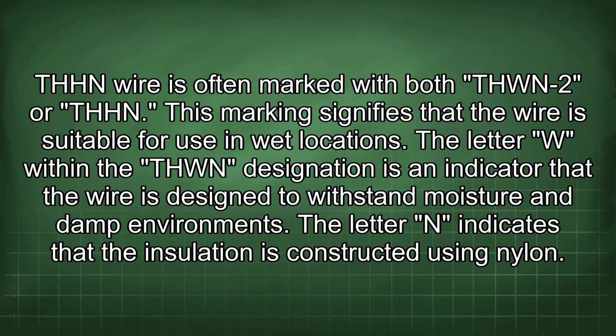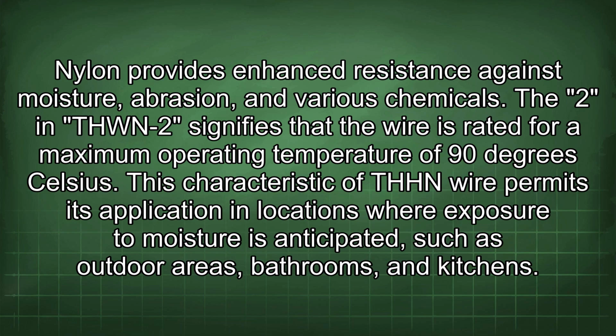THHN wire is often marked with both THWN-2 or THHN. This marking signifies that the wire is suitable for use in wet locations. The letter W within the THWN designation is an indicator that the wire is designed to withstand moisture in damp environments. The letter N indicates that the insulation is constructed using nylon. Nylon provides enhanced resistance against moisture, abrasion, and various chemicals. The 2 in THWN-2 signifies that the wire is rated for a maximum operating temperature of 90 degrees Celsius.